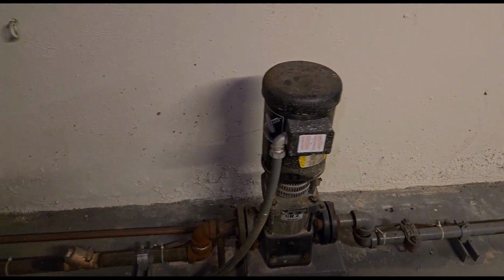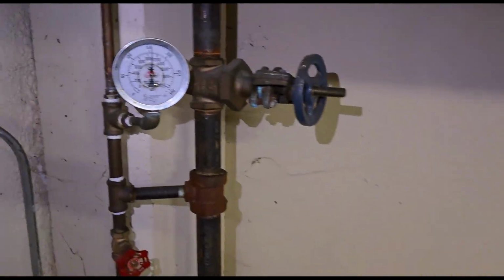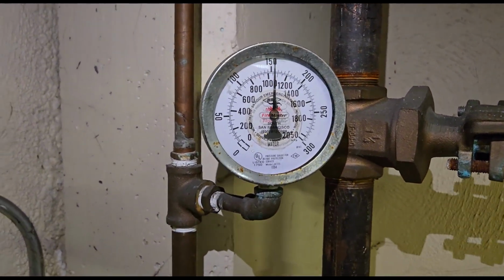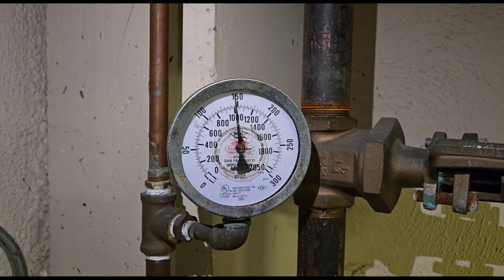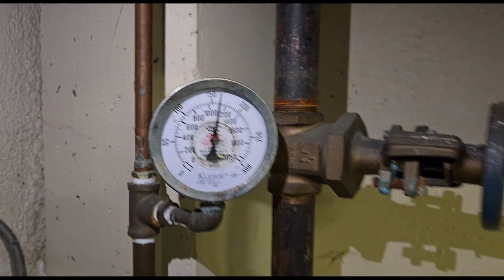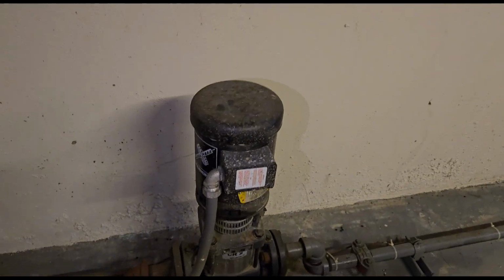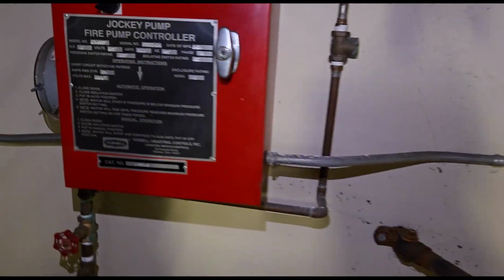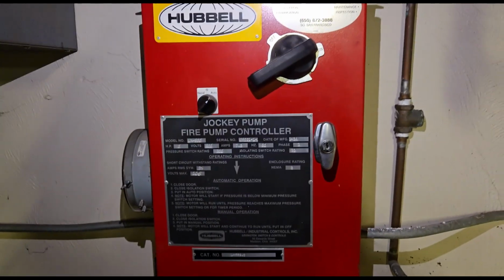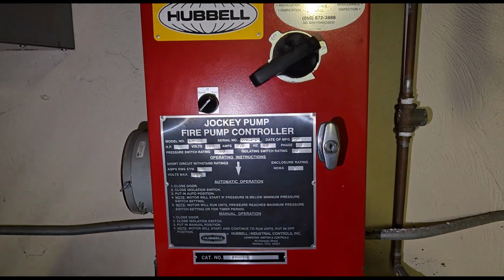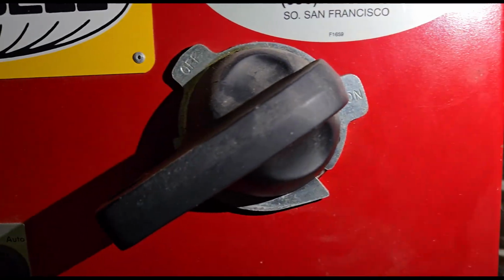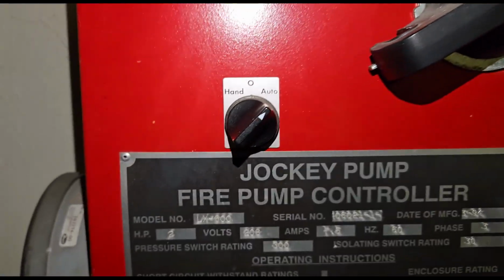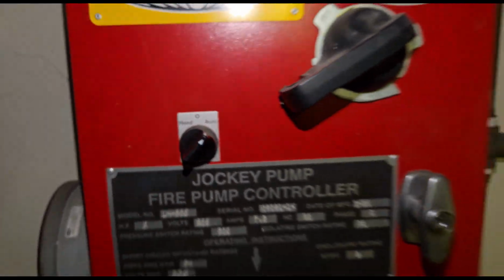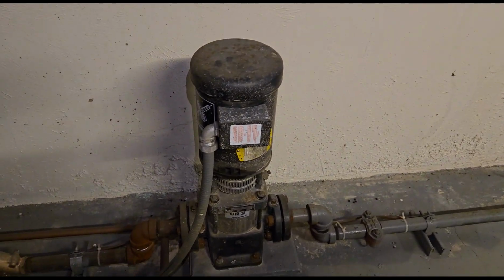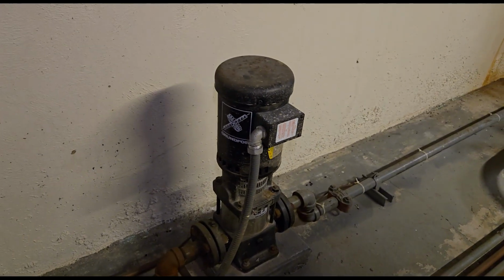Little guy right here. You can see whenever the pressure drops, it's gonna kick on. There you go. It's just maintaining the flow right now. Jockey pump controller's still on. Again, sorry for the lighting. So it's on the on position and it's set to auto. So it just keeps bumping up the pressure for us while we're doing our flow testing.